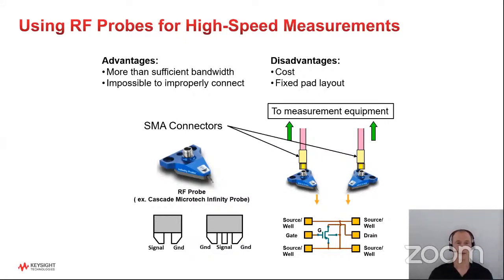Again, if you want to make really clean RF measurements, and of course, in parametric tests, we're not oftentimes making true RF measurements, but if you want to make really clean pulsed measurements, using an RF probe will give you the best results. That's definitely clear, because these things are designed to go much higher, much faster than anything we're doing in parametric test. So they have plenty of bandwidth. You can't misconnect them. The disadvantages, again, are cost and the fixed pad layout. So again, it depends what you're doing and what you need to do.